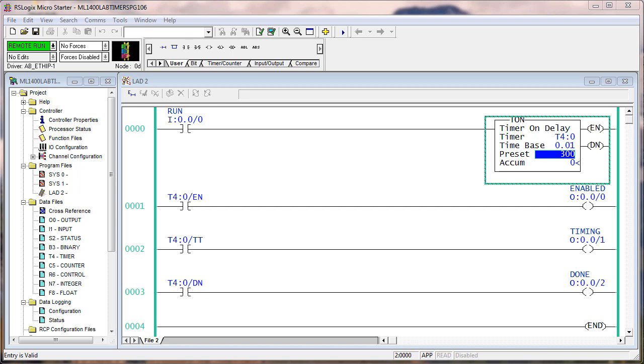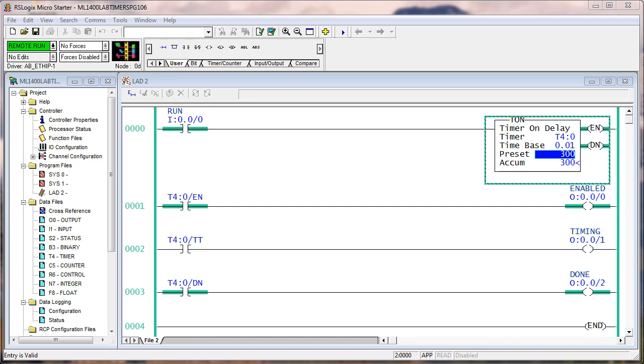There is only one type of timer data type, and all of the timer instructions — TON, TOF, and RTO — all use that same data, specifically the timer timing and done bits. When you're instructing a timer data type with a TON, the timer timing bit is on from the time it's enabled until the done bit comes on. The done bit comes on when the timer timing bit goes off — the instant that the accum equals the preset. It's no longer timing but it is still enabled as long as rung zero is true.